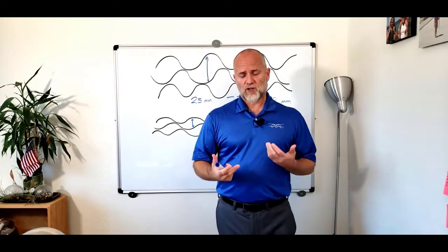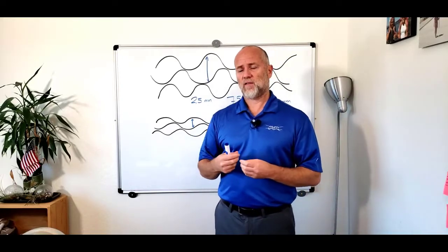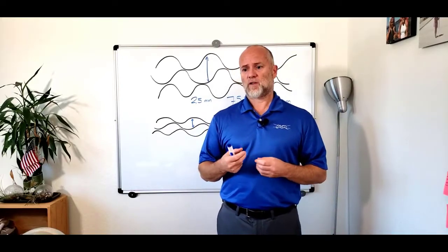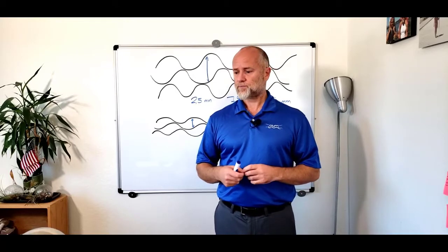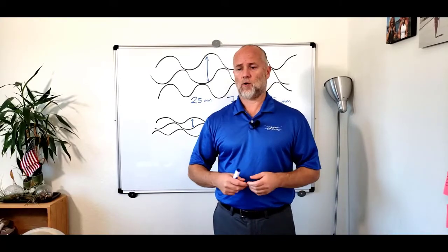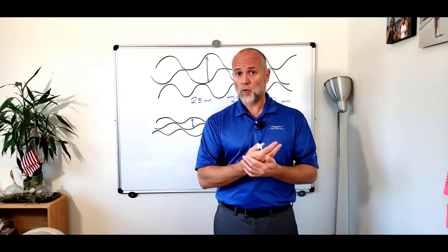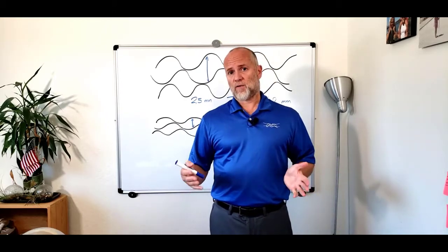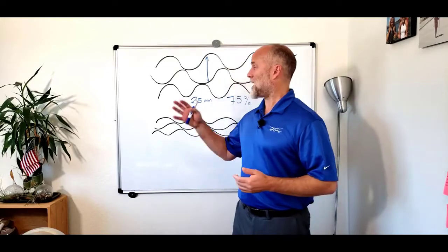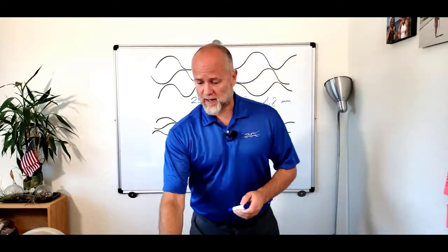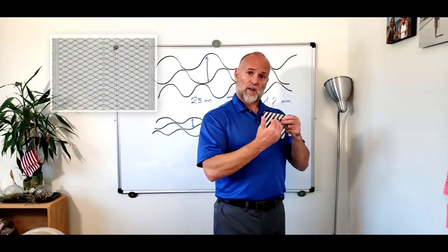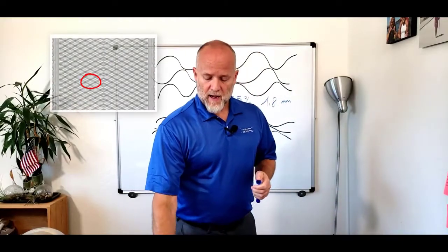And you have to imagine that on top of that, if you have fluffy or soft particles like paper bags or plastic sheets, they actually are pushed through the holes of the strainer, and they end up in the heat exchanger at the contact points of the plates.